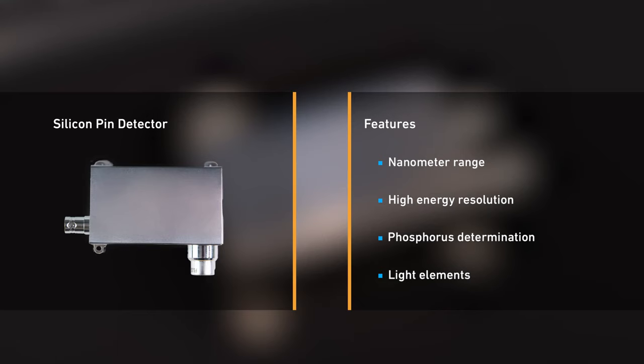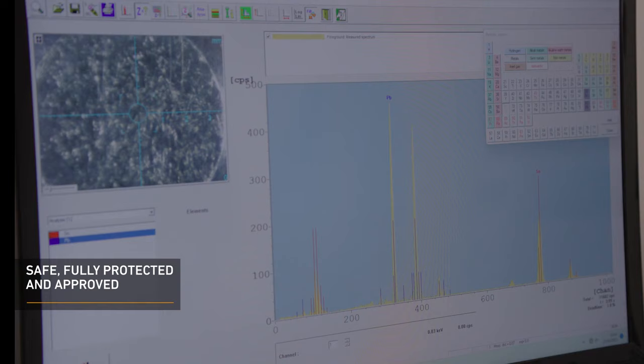It is one of the best detectors for measurement of light elements such as aluminium, silicon, phosphorus, or chlorine. As for safety, the FischerScope X-Ray XAN 250 is a fully protected instrument with type approval according to current radiation protection legislation.